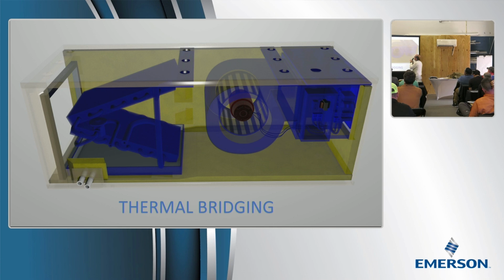Okay, so thermal bridging. Why don't we recess the screws so that we can pinch the insulation down? Because if the insulation is 3/4 inch, but then we put a metal drain pan on it and squish it down, that's what most air handlers have. And particularly above this cold metal 16 gauge enclosure. It's a heavy gauge for its UL approval because it's got an electric strip heater. And guess what that heavy gauge metal does with heat? It moves it right on through. It doesn't have any thermal storage. It's just going from one place to another.